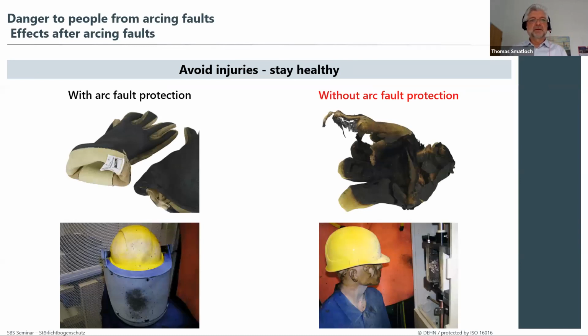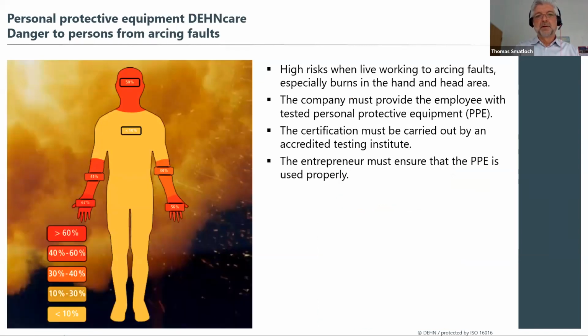Good. What are the effects after such an arcing fault? Therefore, we have this comparison between good material on the left-hand side and insufficient material on the right-hand side. Here we have special gloves tested for this purpose. They can withstand certain energies of an arc fault. And you can see also this face shield in this case, protecting the face and the upper part of the body of the installer. On the right-hand side, you see what happens when you use insufficient material, which can burn, get holes, and will lead to injuries for the operating personnel.